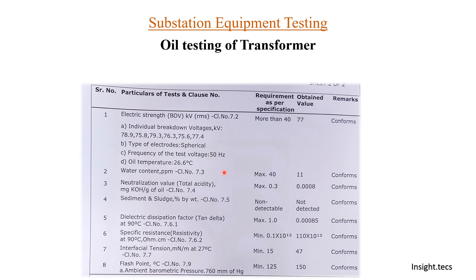These are the sample results taken from the transformer and tested in a laboratory. We discussed the first four in the last video already: BDV was 77, it has to be more than 40 — that confirms. Next is water content in ppm, maximum allowed is 40 but we are having 11 — that is okay. Neutralization value maximum should be 0.3, and what we obtained was 0.0008 — that confirms. Sludge was not detected — that is okay.